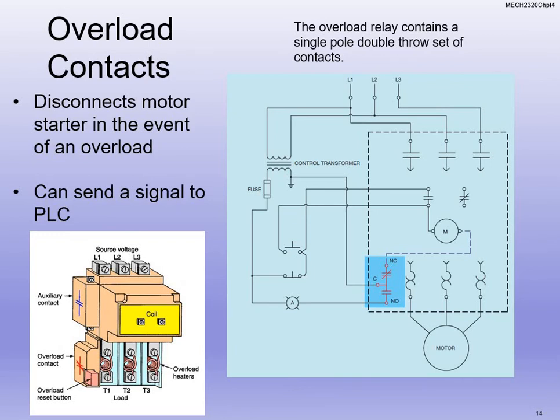And then each one of those has a contactor that goes with it. You see those at the top of the diagram there. So when those open up, the PLC actually knows, oh, we're tripped or the motor's off. So it's very, very important that we have those. That's for communication purposes. The contactors themselves aren't what's protecting the circuit. The overload relay, the thermocouples that you see there connected to the motor are, but those are tied to contactors on there. So they all work in unison. So that's really why we have those on there.